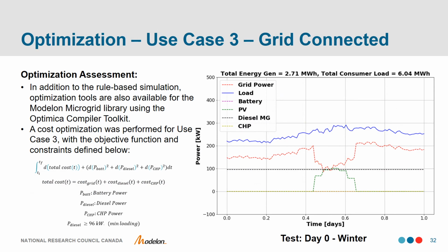In addition to the rule-based simulation, optimization tools are also available for the Modelon Microgrid library using the Optimica compiler toolkit. A cost optimization was performed for use case 3 with the objective function seeking to minimize the total cost while assigning a penalty to rapid changes in battery power, diesel power, or CHP power. In addition, the diesel generator was constrained to operating at or above its min-loading level of 96 kilowatts.